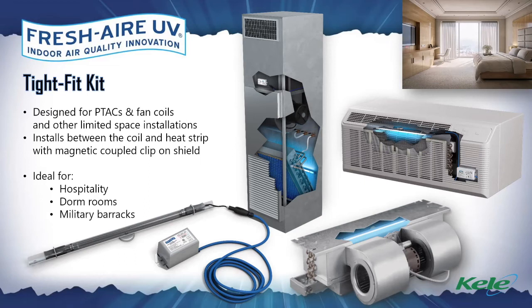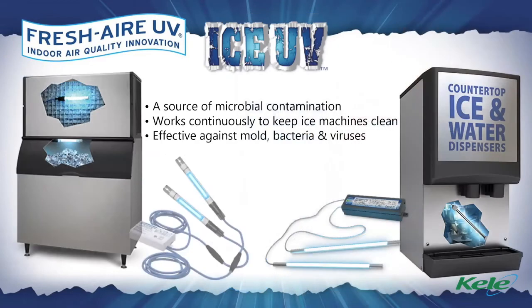So when a hospital or a hotel or an army barrack or a dormitory is looking to do something to improve the air quality inside the room without having to install a self-contained portable unit, which could get very, very costly, the tight fit kit is a great solution to make their own AC system into an air treatment system. And that's essentially what we want to do in all these applications: take advantage of the fan that you're already using and install a secondary UV lamp in order to address the air as it continually recirculates through the room.